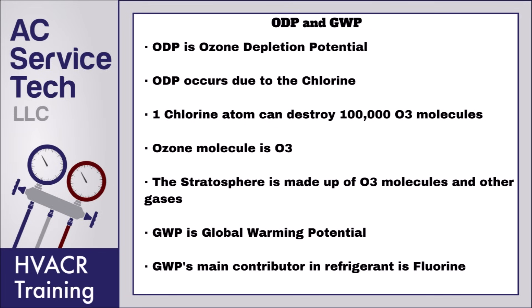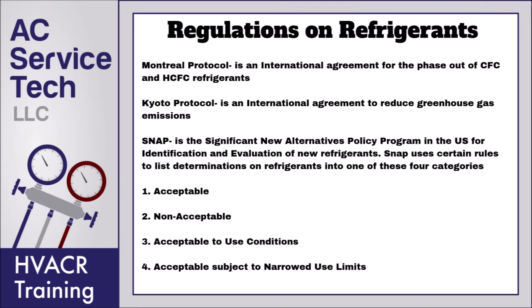Some of the older refrigerants had ODP and GWP. ODP is ozone depletion potential and GWP is global warming potential. Ozone depletion potential occurs due to the chlorine in the refrigerant being released into the atmosphere. One chlorine atom can destroy 100,000 O3 molecules. The ozone molecule is made up of O3 and the stratosphere is made up of O3 molecules and other gases. GWP's main contributor in the refrigerant is the fluorine. Because of that, the Montreal Protocol was an international agreement for the phase out of CFC and HCFC refrigerants, which both led to ozone depletion potential as well as global warming potential. The Kyoto Protocol was an international agreement to reduce greenhouse gases, which included refrigerants with GWP.